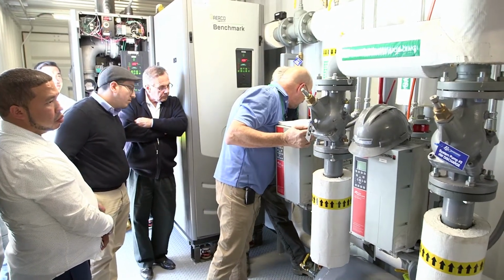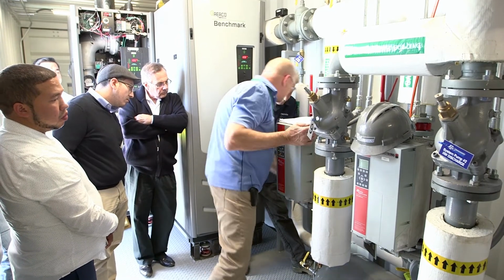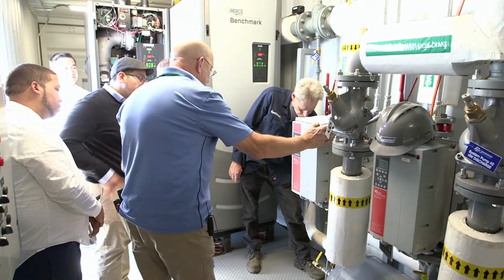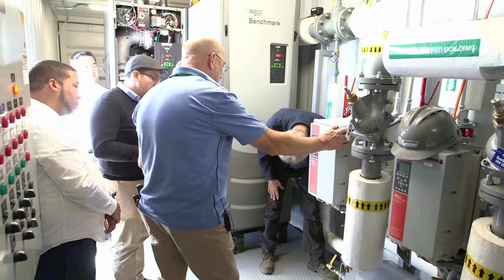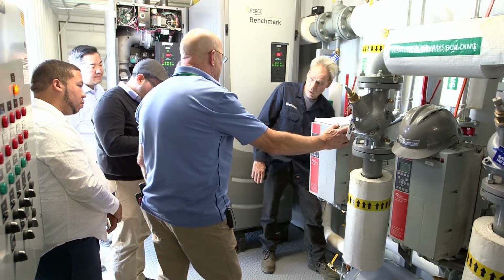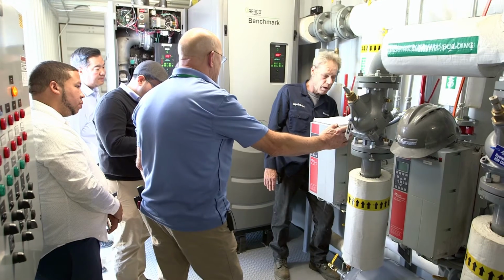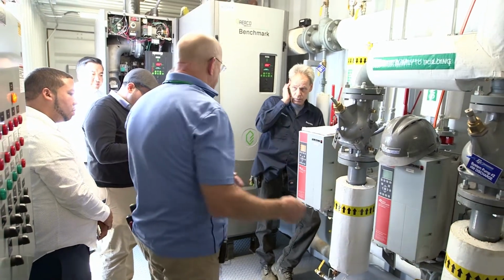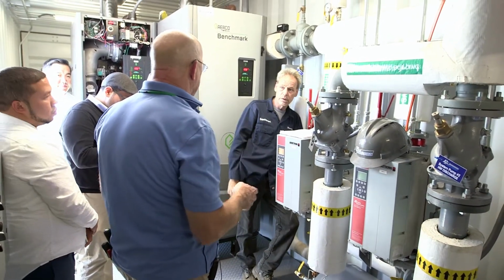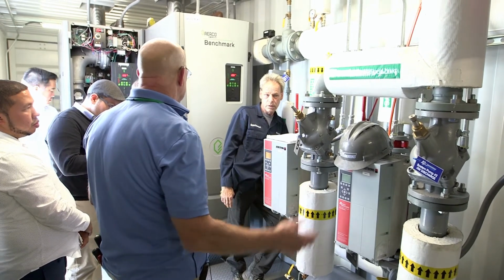And once a year, this strainer in here should be pulled out and cleaned. Once a year. You can blow them down once a month, but once a year you should really pull that strainer and make sure it's good. Because that's, like the heat exchangers, that's going to prevent any baseboard and convectors in the building from getting clogged up with gunk.